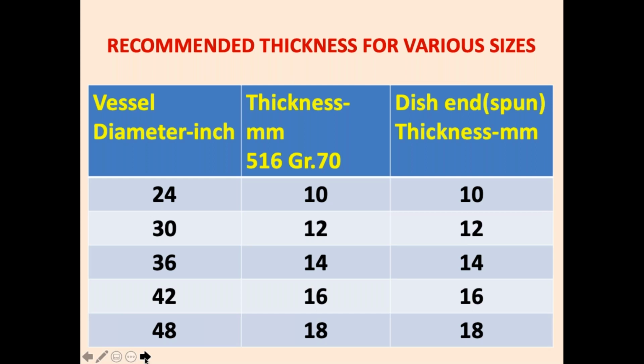And the dish end is normally one size higher material because people use formed dish ends, made by pressing, and when you press it, at the knuckle radius the thickness comes down. To compensate that, they use one size thicker. But if you get a spun dish end, then it is not necessary. You can do these calculations and you can reconfirm my opinions.